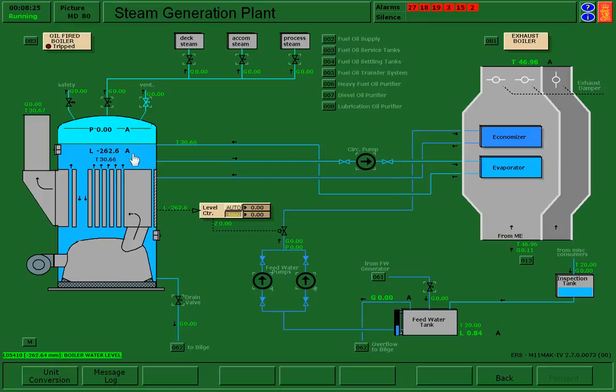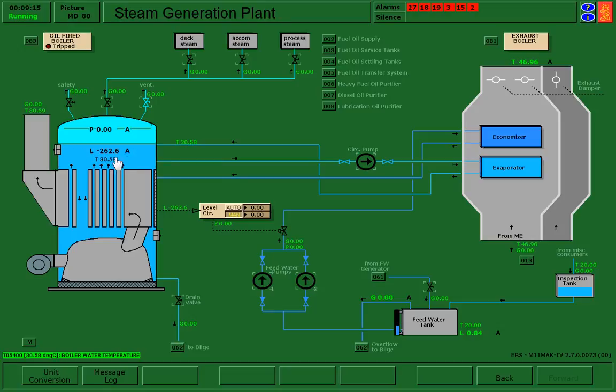If we look at the level inside of our boiler right now, we are low. The negative sign, negative 262, means that our water level is below where we want to be. Our target would be zero. So let's fill up some water into the boiler before we get started.